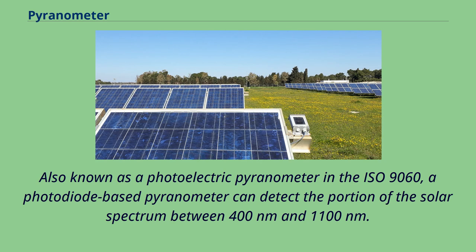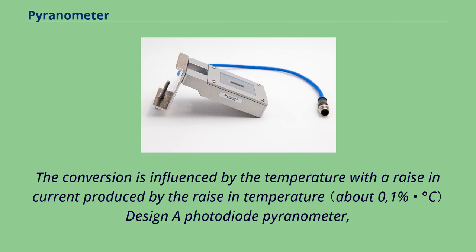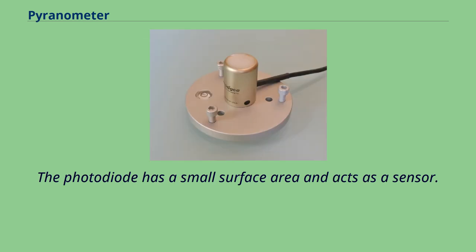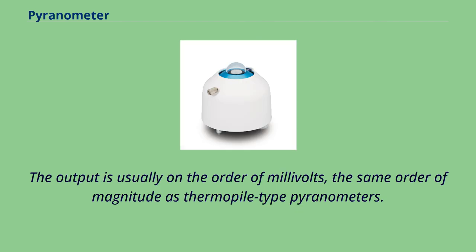Also known as a photoelectric pyranometer in ISO 9060, a photodiode-based pyranometer can detect the portion of the solar spectrum between 400 nanometers and 1,100 nanometers. The photodiode converts these solar spectrum frequencies into current at high speed, thanks to the photoelectric effect. The conversion is influenced by temperature. A photodiode-based pyranometer is composed of a housing dome, a photodiode, and a diffuser or optical filters. The current generated by the photodiode is proportional to irradiance, and an output circuit such as a transimpedance amplifier generates a voltage directly proportional to the photocurrent, typically on the order of millivolts — the same order of magnitude as thermopile-type pyranometers.